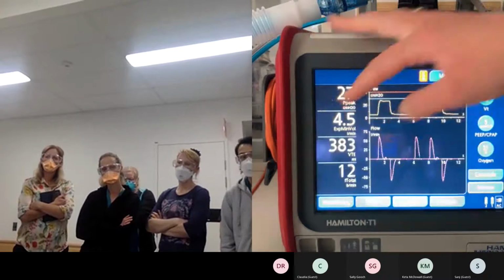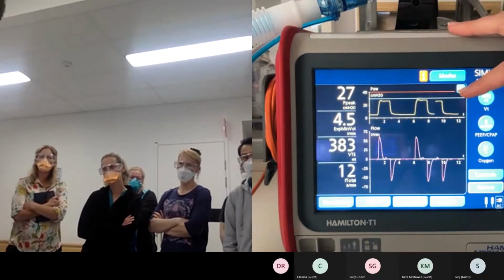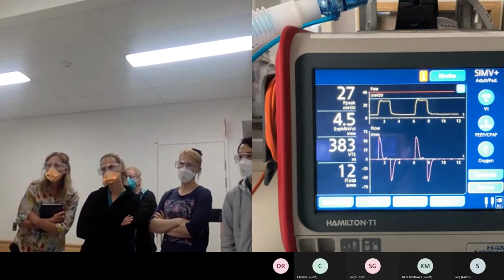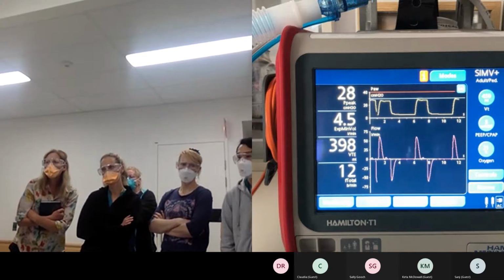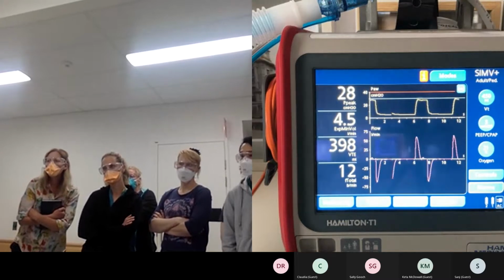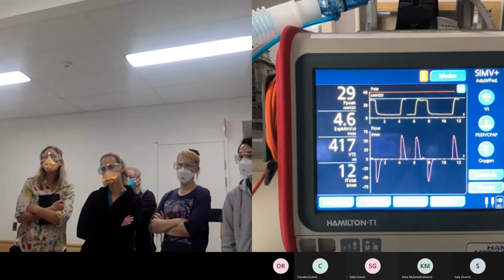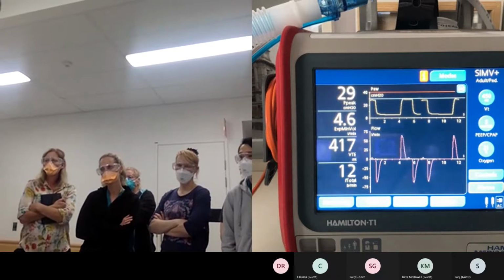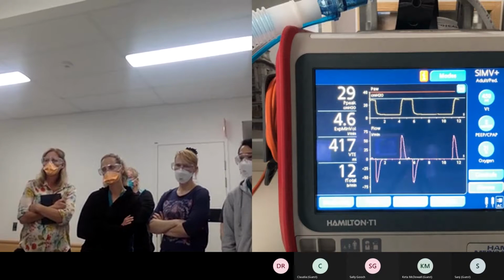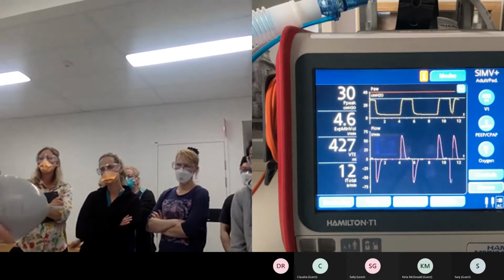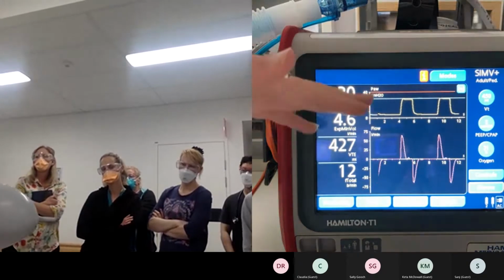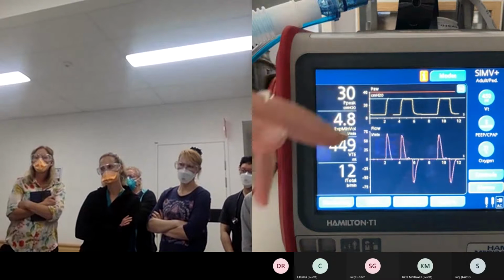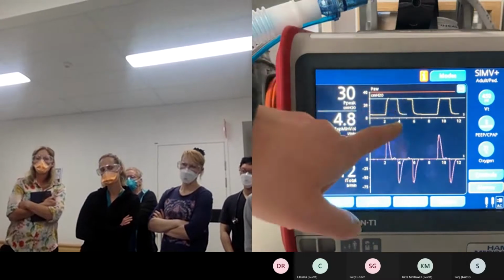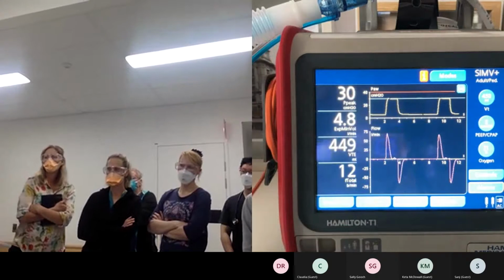What that correlates to on your pressure waveform is a red line. So the difference between the red and the blue is, think of it as a hard and a soft limit. The red is your hard limit or dump point. The blue is your soft limit, and that's where the breath will deliver up to. Okay, so the ventilator will only deliver a pressure to the blue line. The breath will still be delivered in length. You may not hit your target volume.